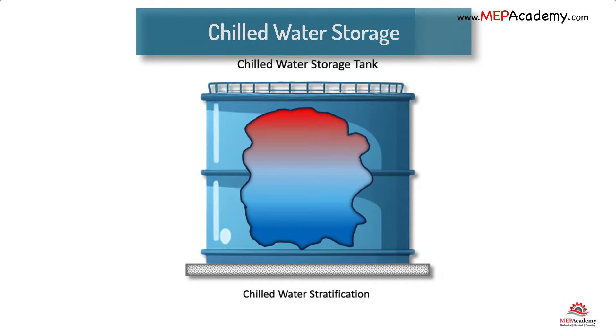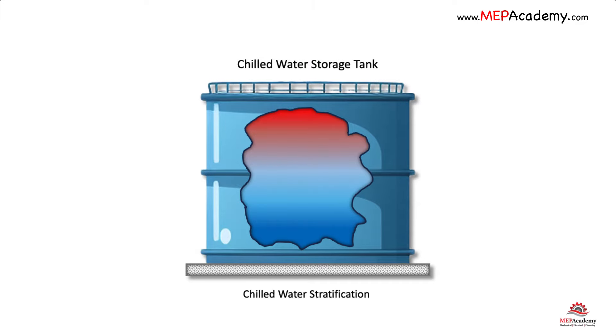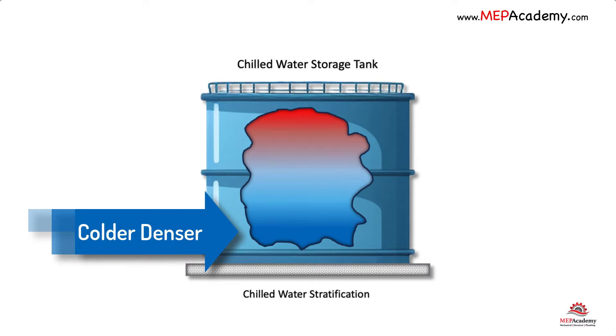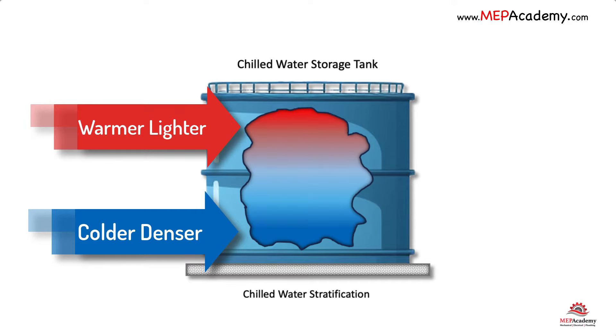Chilled water thermal stratification is a sensible heat approach. Stratification is used within the tank as a strategy for thermal layering of the stored water. Colder water is denser and will settle toward the bottom of the tank, while the warmer water will naturally seek to rise to the top. As water enters and leaves the tank, it's important to make sure not to disturb or mix the stratified layers. This is done with the use of diffusers within the tank on the inlet and outlet piping.